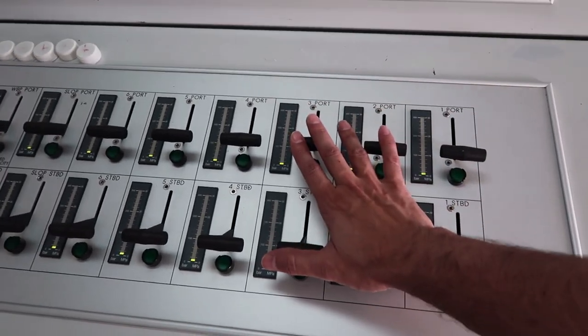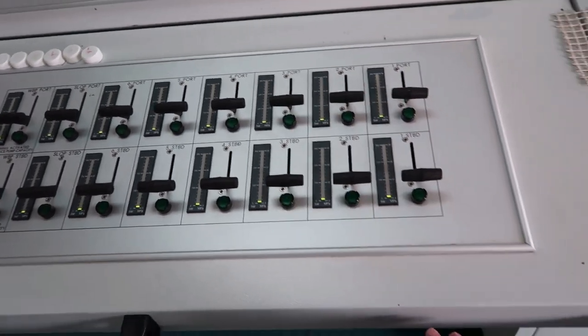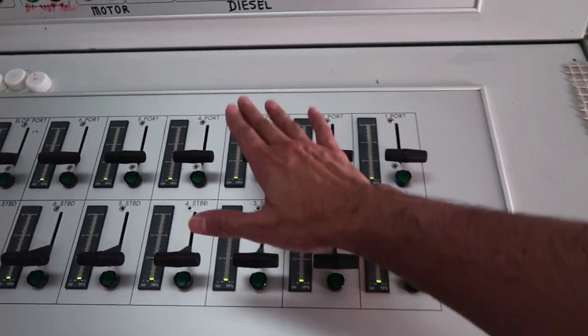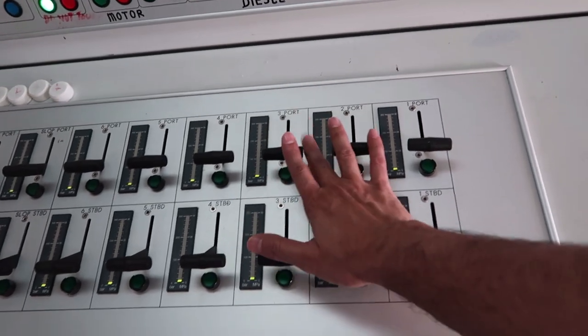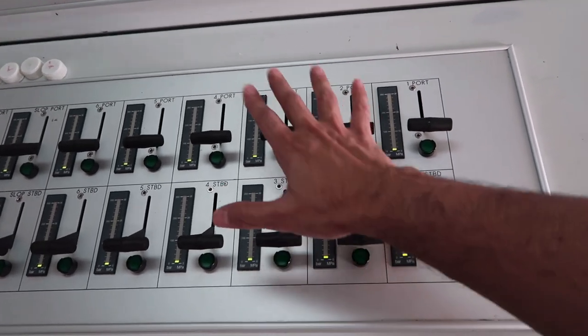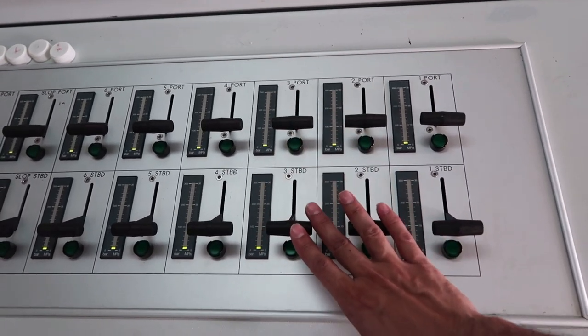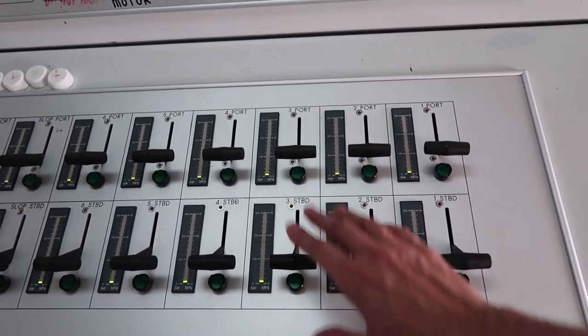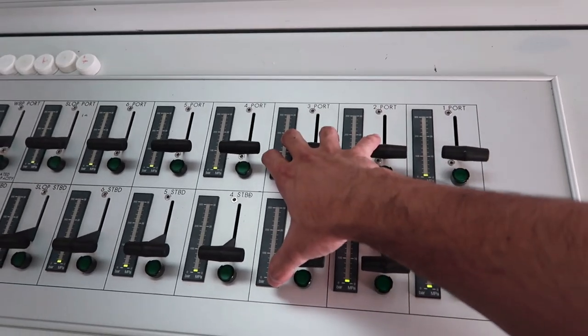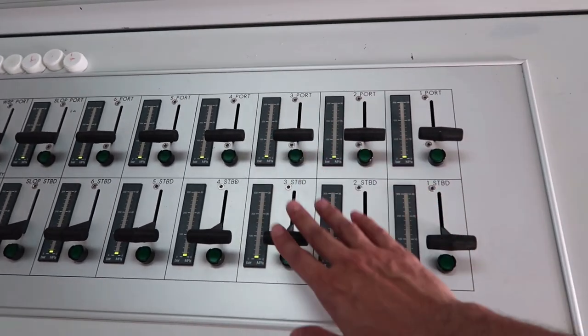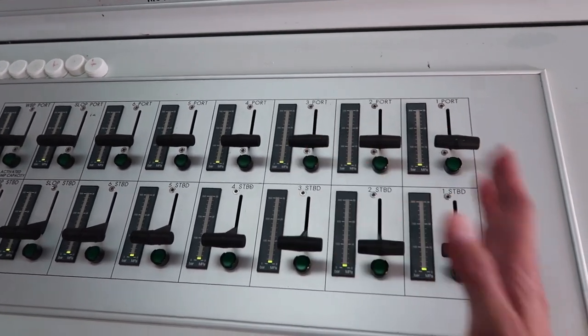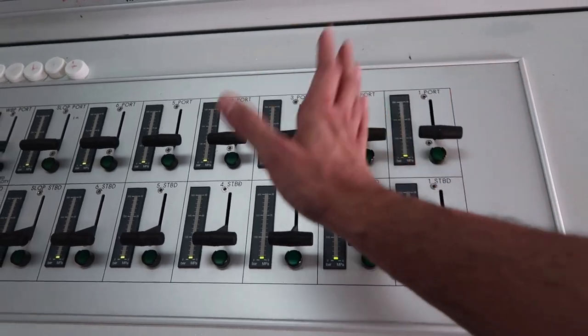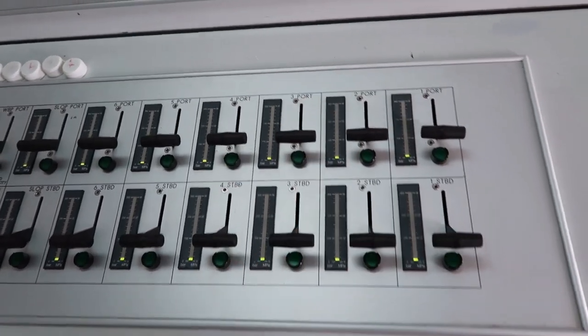But if few pumps are in the same system, that means if these tanks are connected on the deck via common line, then it is beneficial to keep them at same pressure. Otherwise one of the tanks which is on lower pressure may start filling back cargo instead of discharging.